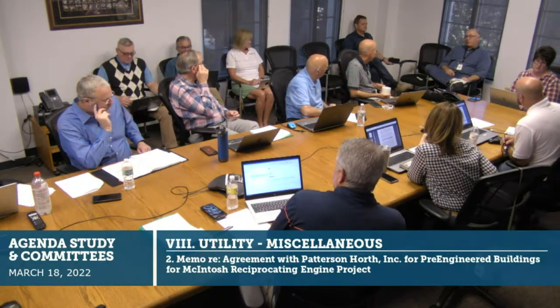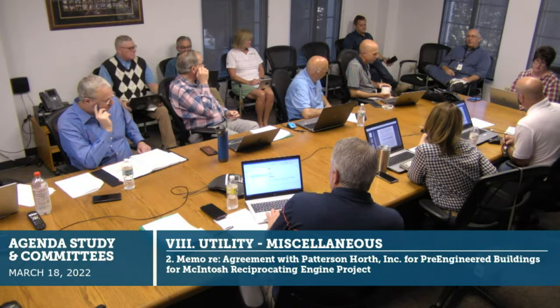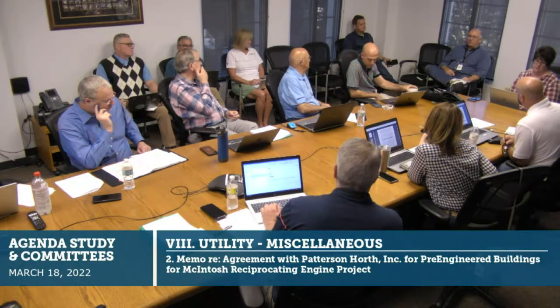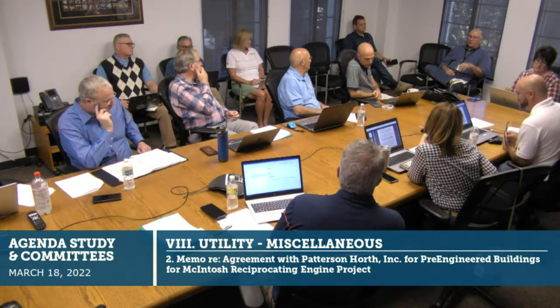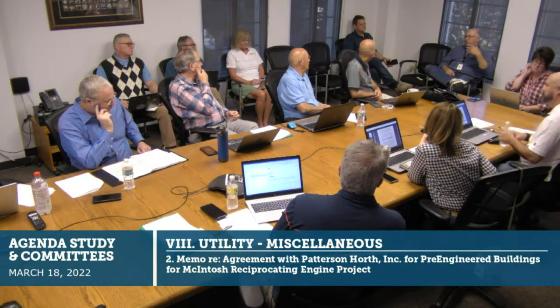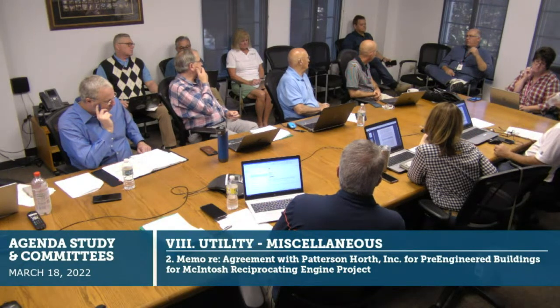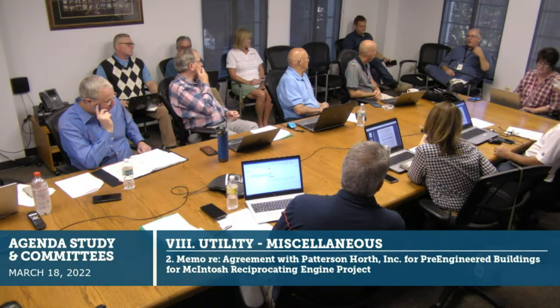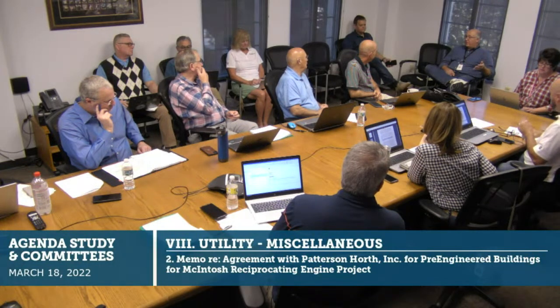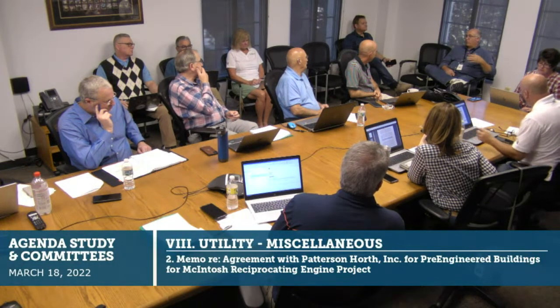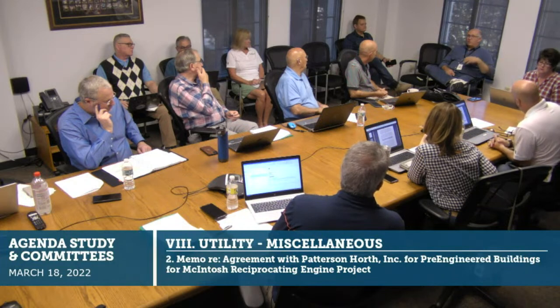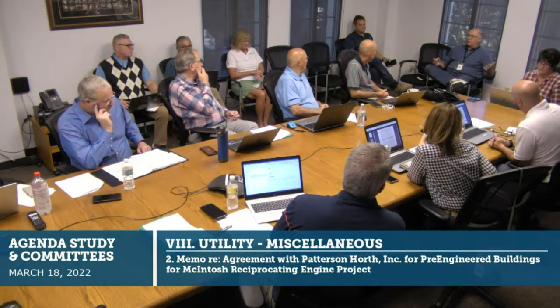Not all building manufacturers have the know-how to build what's required for the Rice engines because of the sound situation. You still have huge penetrations in the wall for the exhaust duct and intake duct. The building ventilation itself, along one wall, we're going to have 12 ventilators to maintain the temperature inside the building. That's huge—basically a whole wall that has to support itself because the ventilators are going to be holes in those walls.